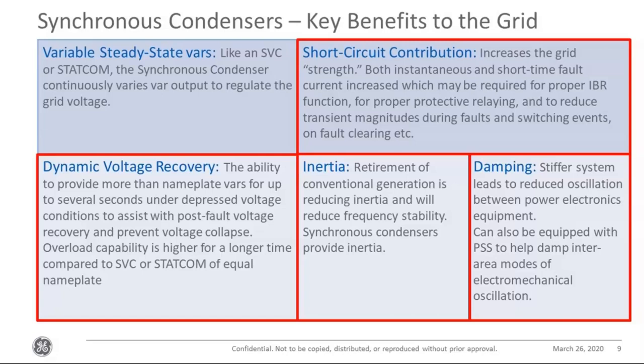The short circuit contribution helps proper operation of IBR, proper operation of your protective elements, and reduces the transient magnitudes. Because synchronous condensers can give increased output for the short circuit and short time after the fault is cleared, it helps with the dynamic voltage recovery. Especially, they can provide a better response even under depressed voltage conditions, which is helpful. And that performance is usually better than SVC or STATCOM of the same nameplate rating. They help increase the inertia, especially if they're equipped with a flywheel.